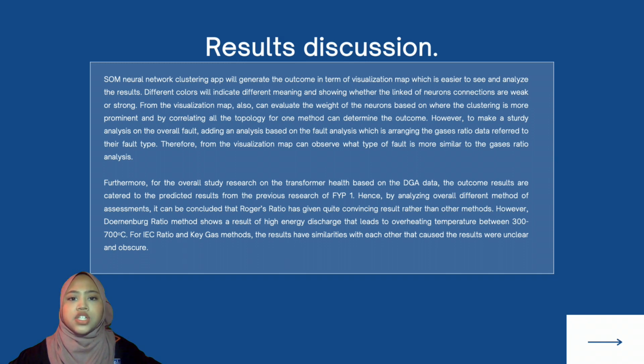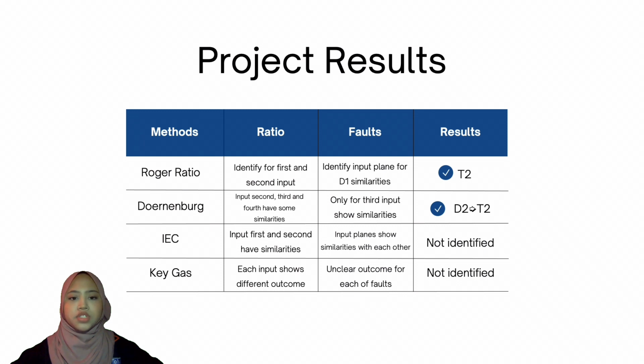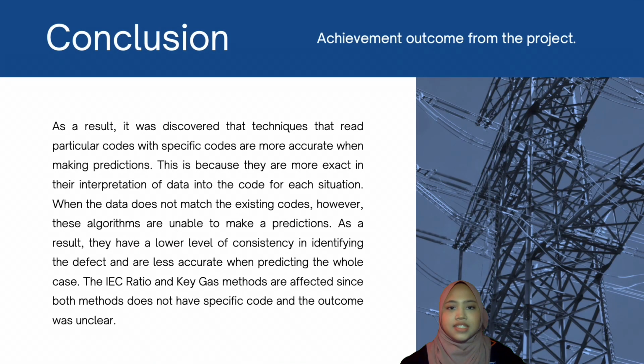Furthermore, for the overall study on transformer health based on the DGA data, the outcome results are compared to the predicted results from the previous research in Final Year Project 1. Hence, by analyzing the different methods of assessment, it can be concluded that Rogers ratio has given quite convincing results compared to the other methods. However, the Doernenburg ratio method shows a result of high energy discharge that leads to an overheating temperature between 300 and 700 degrees Celsius. For the IEC ratio and key gas methods, the results are similar to each other, which caused the results to be unclear and obscure. To give a clearer observation of the visualization map results, here is the table shown for each of the methods with the results.